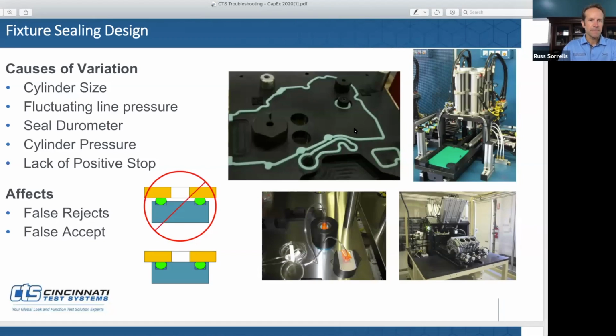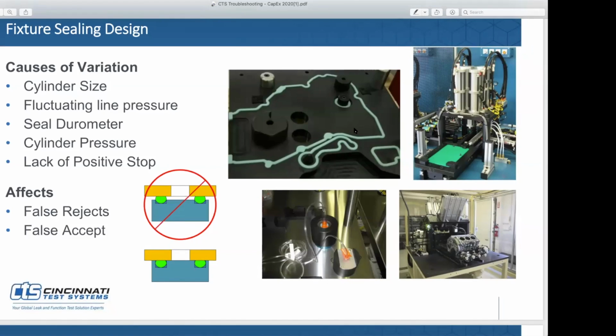And then seal durometer, like we were saying earlier, having the right durometer so that you're allowing it to compress and not compress too much, where it causes excessive wear. And if you have high pressures, it doesn't just have to be a 70 durometer. It can actually be a 70 durometer with fiber fill. That way you give it some tensile strength so it's not cutting easily.